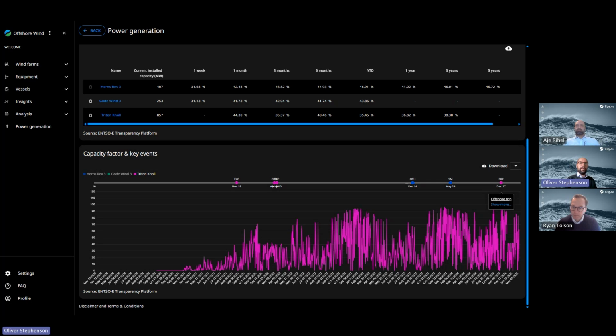Yeah, maybe if I pick that one up, and RJ, if you've got any comments, feel free. I think the short answer is yes, turbine size definitely matters - it's a question of physics, no more complicated than that. The issue is if you get a cable failure on the export cable side, it's going to cause big problems. So it's more complex than just asking if it's the turbine megawatt size. There are ways, as RJ mentioned, to build redundancy into these projects, but export cable failure, when it happens, is a fundamental issue and can wipe out some of the gains you get from the bigger turbines.